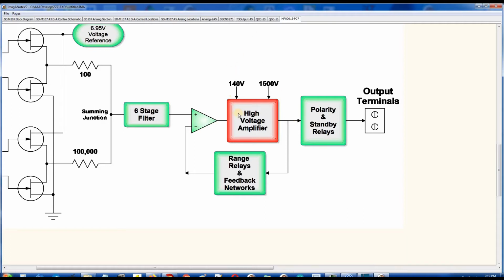Anyway, this high voltage amplifier's got a 140 volt power supply and a 1500 volt power supply when you're in the 1000 volt range. 2 other relays, one for polarity, which just swaps the outputs over to the output terminals, and the standby relay, which just cuts off the output and shorts terminals. I don't think I explained that too well, but a bunch of resistors controlled by relays change the gain of the amplifier so that the right voltage comes out for the range that you picked.